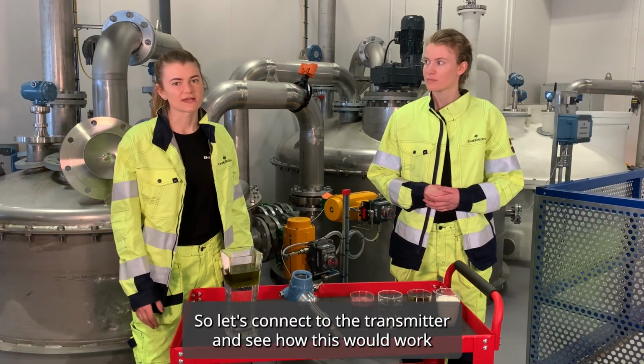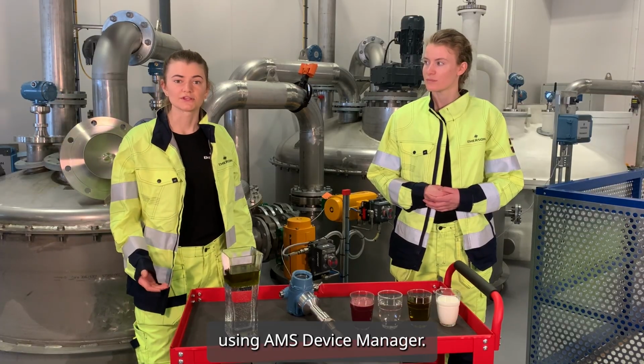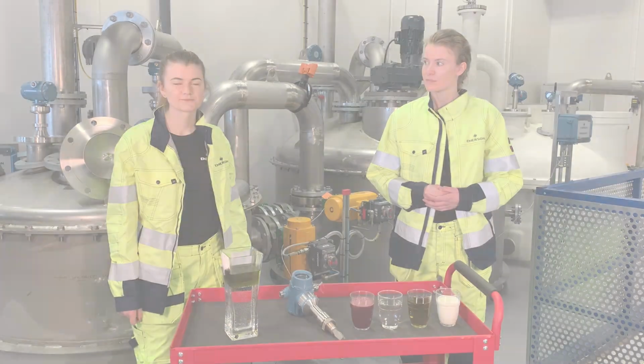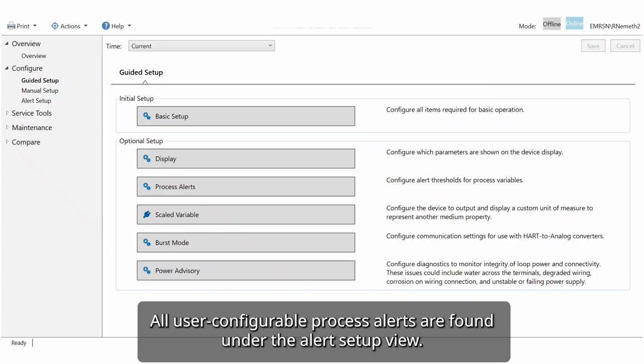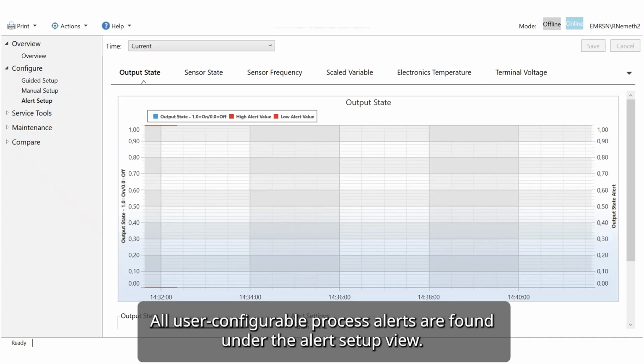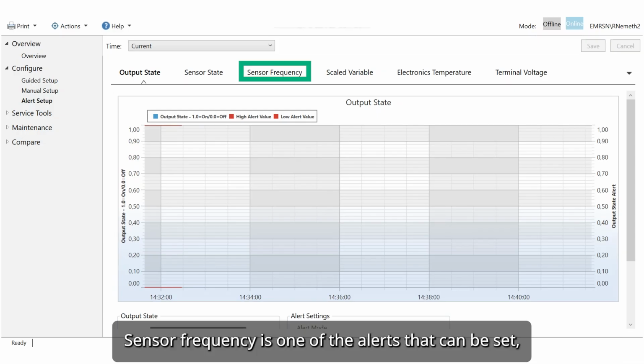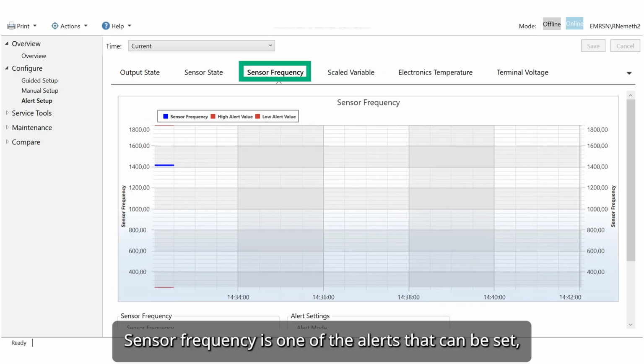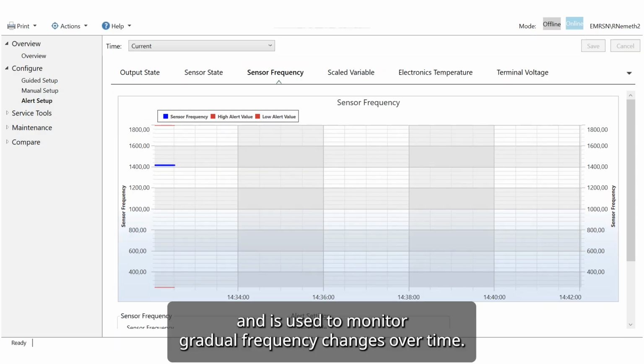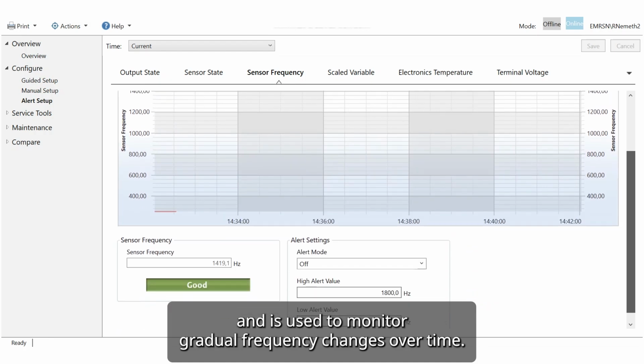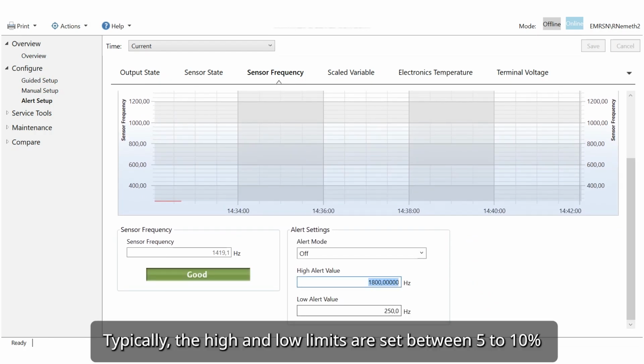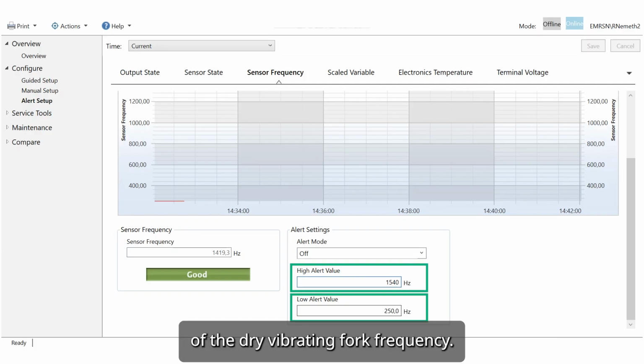So let's connect to the transmitter and see how this would work using AMS Device Manager. All user-configurable process alerts are found under the Alert Setup view. Sensor frequency is one of the alerts that can be set and is used to monitor gradual frequency changes over time. Typically, the high and low limits are set between 5 to 10% of the dry vibrating fork frequency.